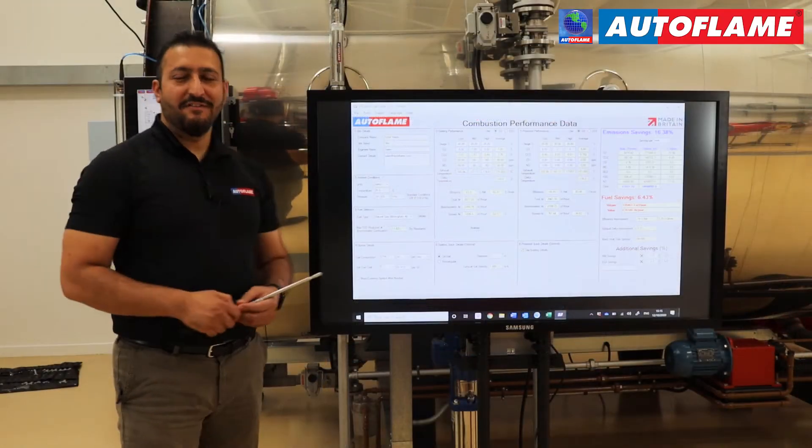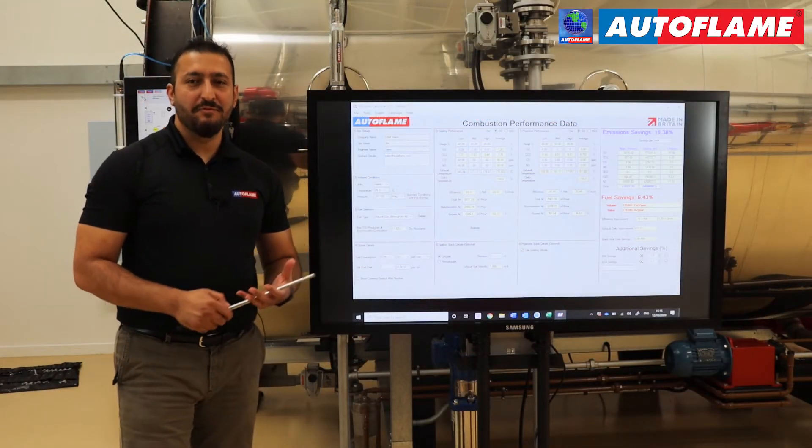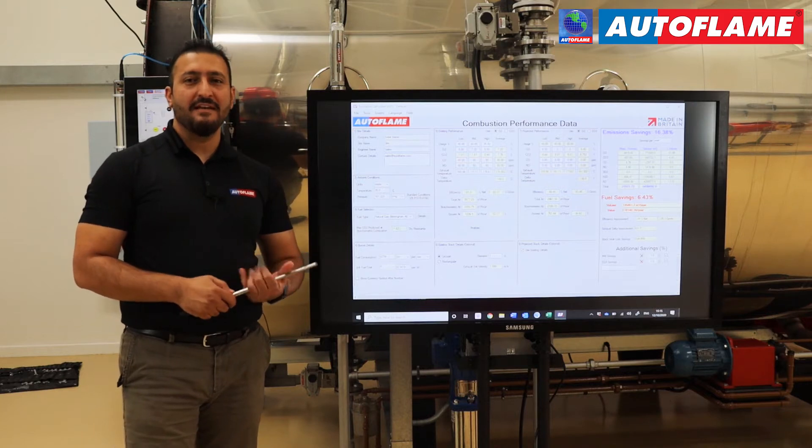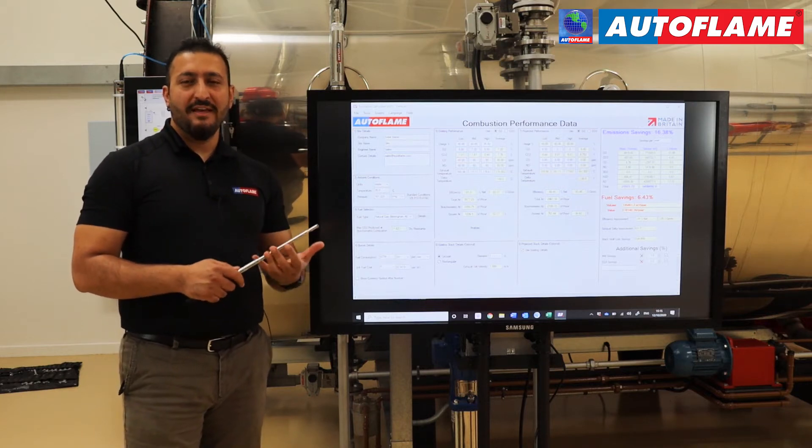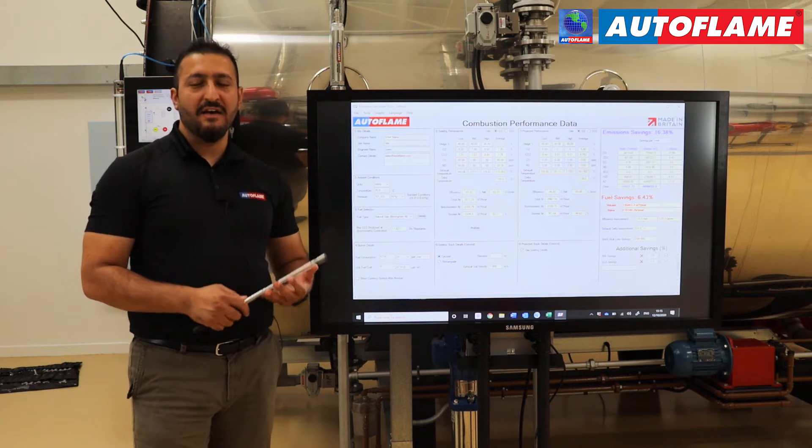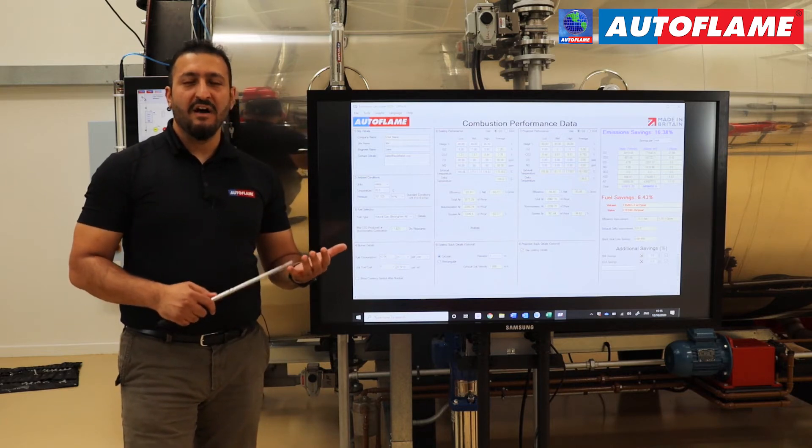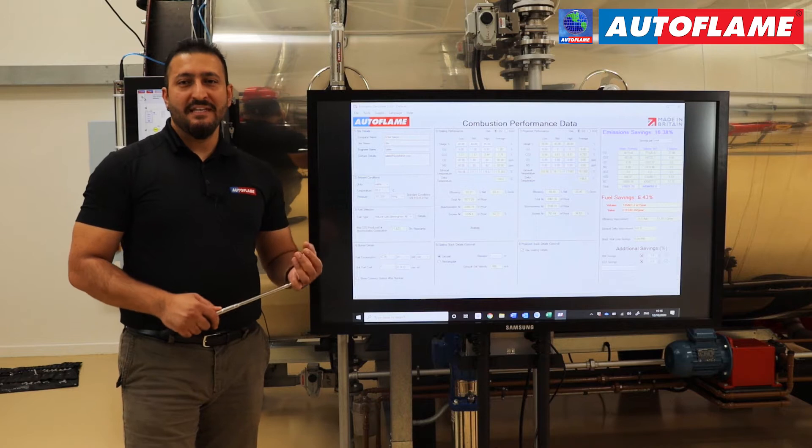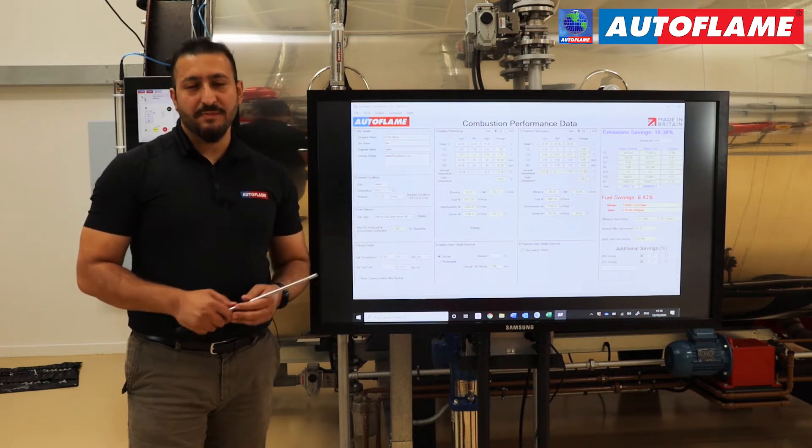In this latest version of the emissions calculator, we made some improvements where the performance data has been put in. So rather than taking an average reading, now we'll put in the data on low fire, mid fire, and high fire positions with a percentage of how long this burner stands on those percentages.